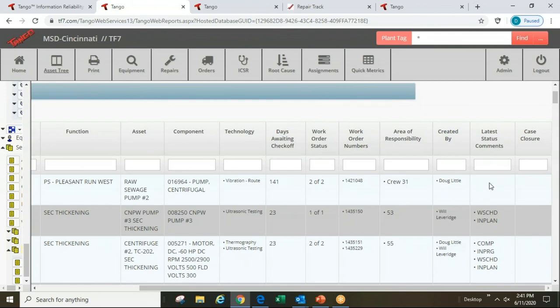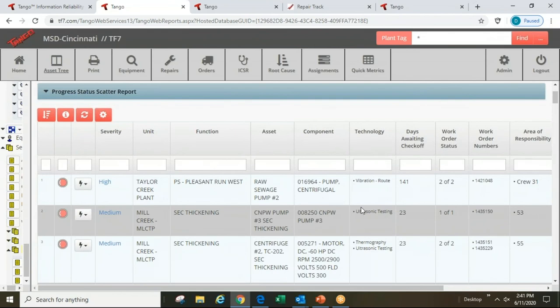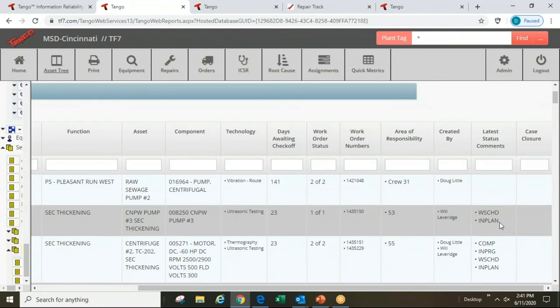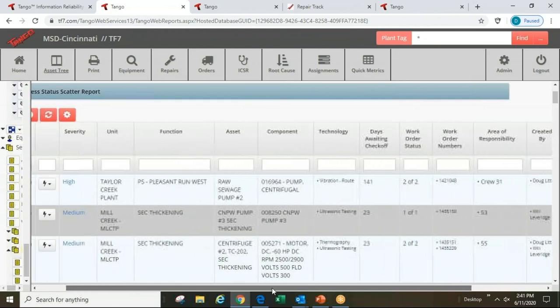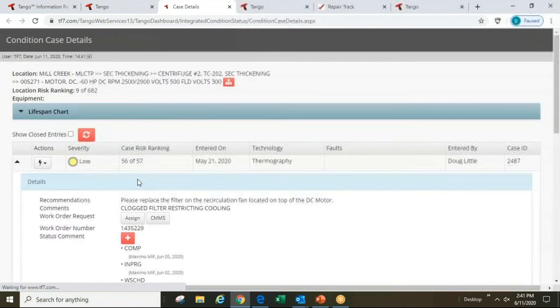There are no status comments explaining why this issue is still open at 141 days. Pump number three shows a fairly new issue from ultrasonics — out there less than a month — with a work order already generated and the status showing it's in plan and scheduled. Another entry shows information coming from two technologies — thermography and ultrasonics — on a motor with a particular problem.